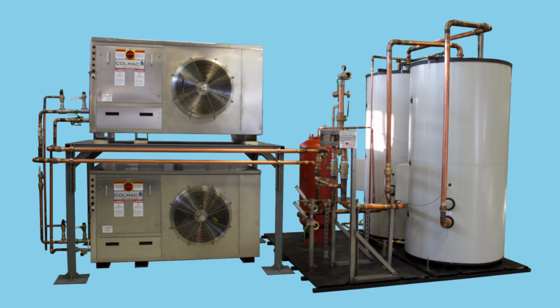Locating thermal storage and temperature maintenance systems. Storage tanks in CHPWH systems are often larger than those in conventional systems and may be installed in series or parallel. This means engineers must plan for the size, weight, and seismic requirements of these tanks, especially if they are placed on roofs or slabs. A floor drain is mandatory for condensate and relief valves, and digital thermostatic mixing valves should be specified to maintain consistent delivery temperatures.